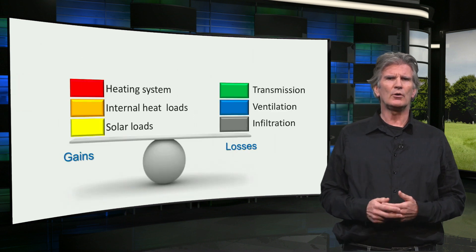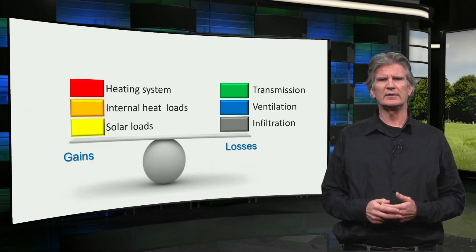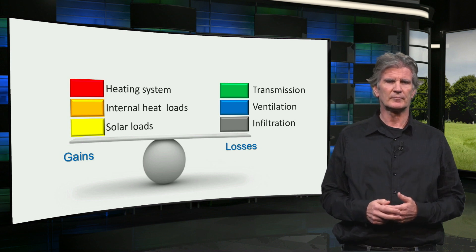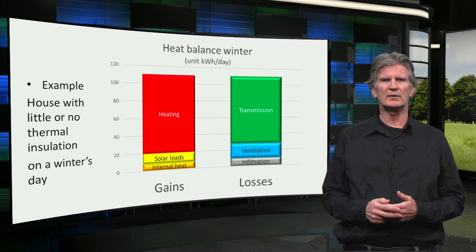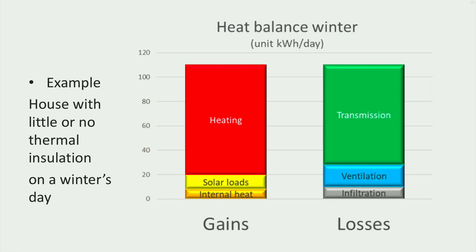Now these are all the parts of a typical heat balance in winter, with the gains on the left and the losses on the right. This is an example of a heat balance for a typical winter's day for an existing dwelling with little or no thermal insulation. As you can see, the transmission losses are the highest. On the gain side, the heating system is the most important. Note that the gains and losses should always exactly be the same.